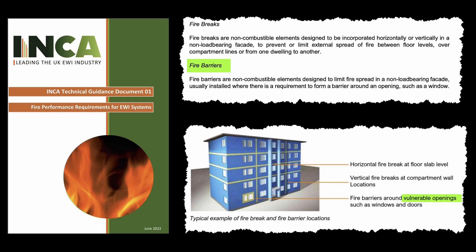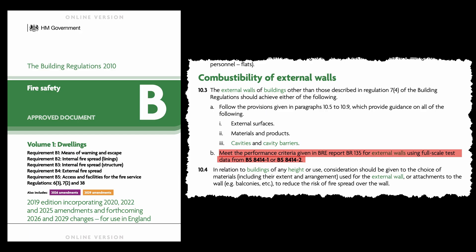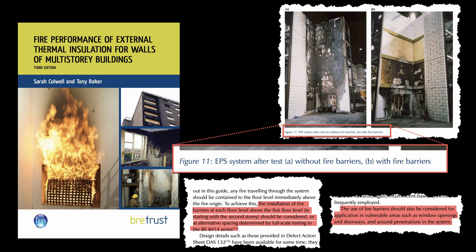So where does this leave us in the UK? Building regulations do allow B-rated combustible materials on facades of a certain height. And because EPS render facades do not have cavities, no cavity barriers can possibly be installed. Fire barriers are not mentioned in the building regulations at all. There are industry bodies like INCA who mention fire barriers at slab levels and in party wall locations. However, the guidance on barriers around openings is vague — calling for fire barriers at 'vulnerable openings' without clearly defining which doors and openings are considered vulnerable.